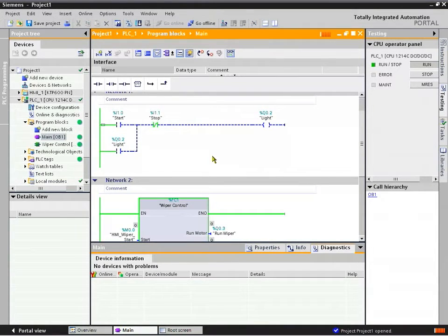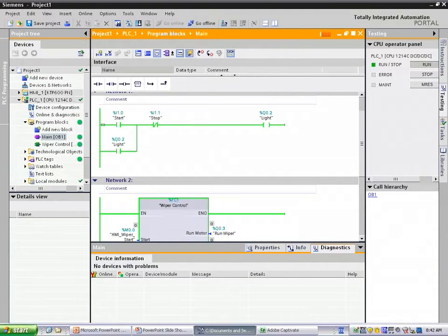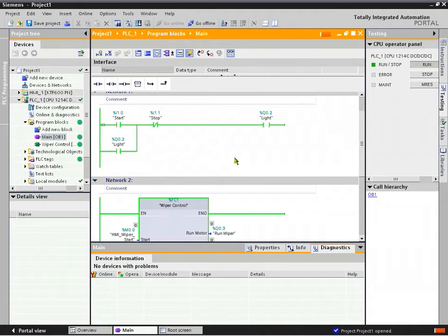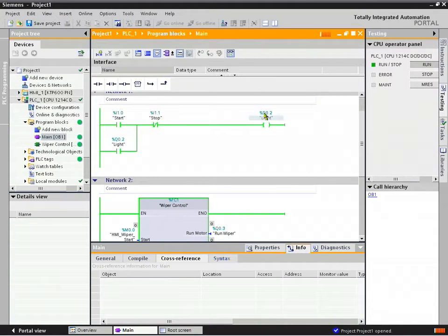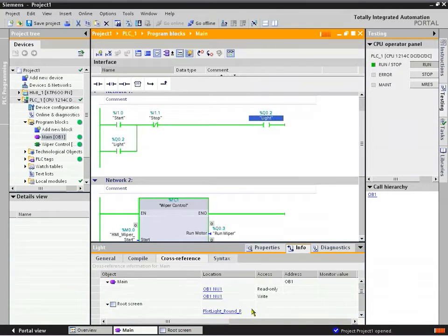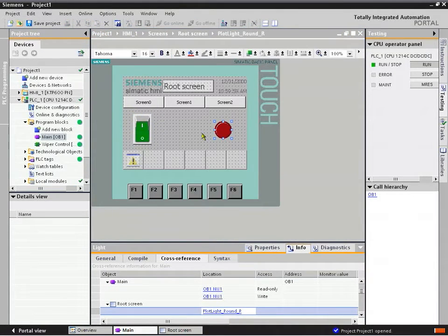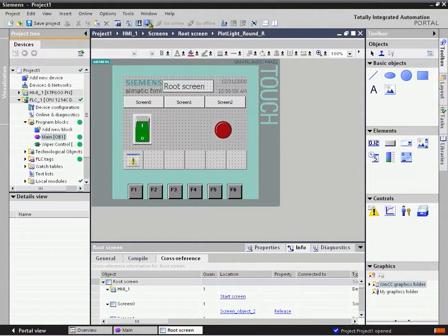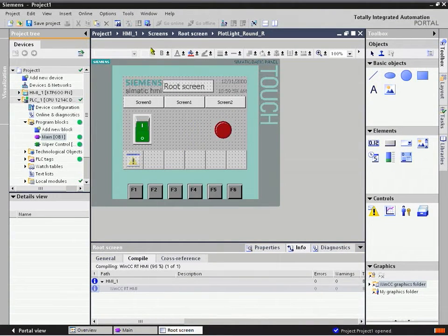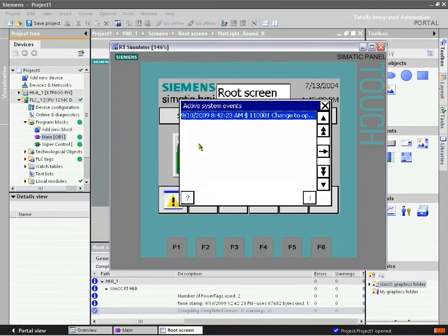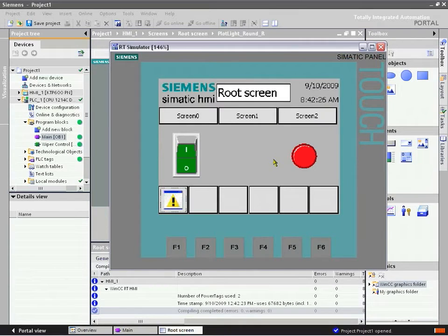In our start-stop sealing circuit, we can start it, and if the light goes on, we can see that on our runtime screen as well. We can cross-reference it over to where it's being used in the HMI and the screen there. We can use the screen in runtime on the PC itself — it has simulation capability right on the PC for the screen project and we can see that it's illuminated. So you've got a lot of powerful debugging tools right at the software connected to the controller, without having to use the devices in the machine or system by themselves.